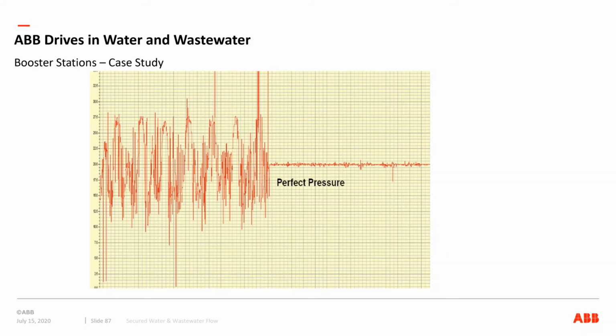You can extend the distance of these. As I said, you can buy filters, you can buy sine wave filters to help you extend the length, and what that does is it takes out the commutations or notching we have in the output. It makes it smoother so that it travels better over motor cable, because one of the things you've got to remember is the motor cable has electrical characteristics. It has impedance and capacitance, so it will increase the V peak and the rise time, but will also slow down the rate of change because of the impedance or resistance in the cable. So it's really a mathematical equation, and this is really where we want to look at an engineer. We really want to get an engineer to help us with that design, to do the calculations, to size everything properly, and really work through it. Those are just some of the concerns that I would throw up there.